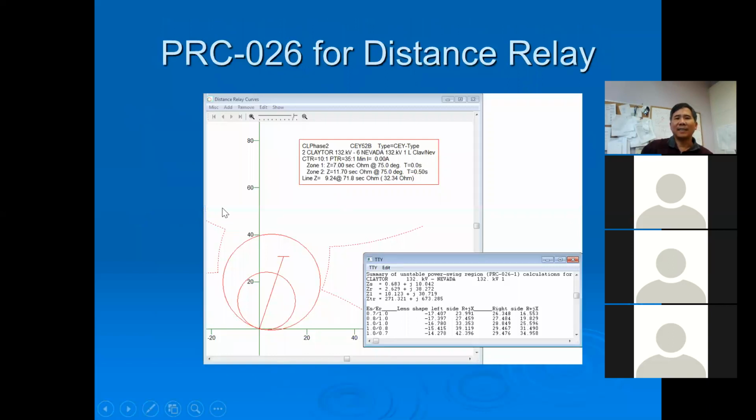As a result, you will have a plot something like that, which I call the butterfly shape, which is the combination of the big circle here for the swing, and also the arc here for the different ratios of the magnitudes of the sources.